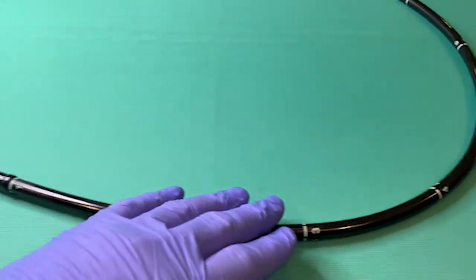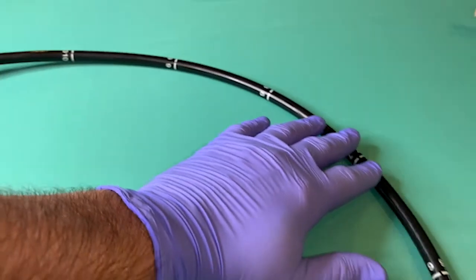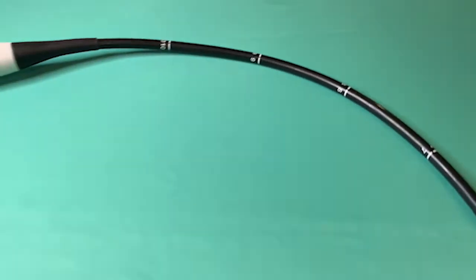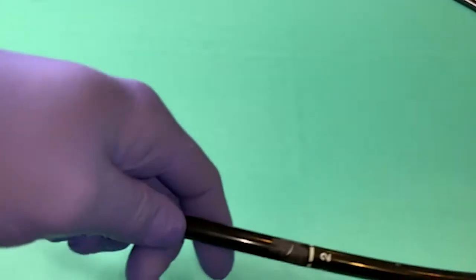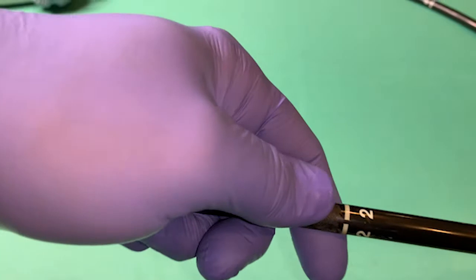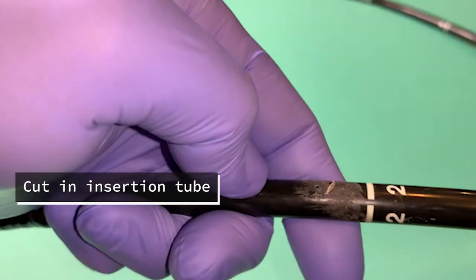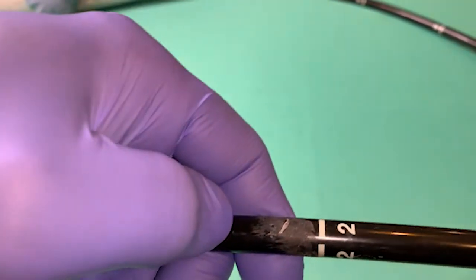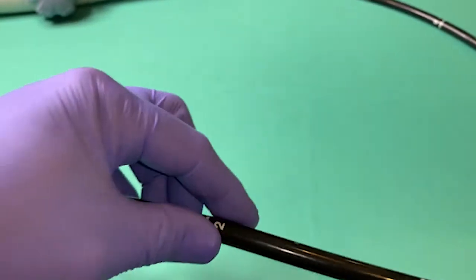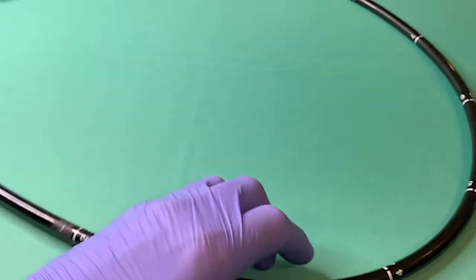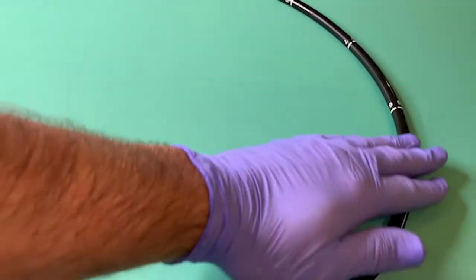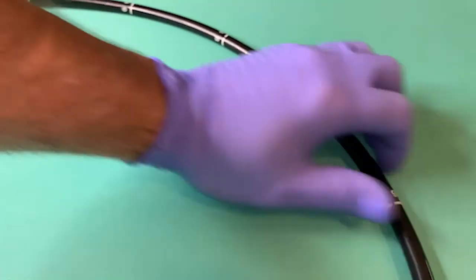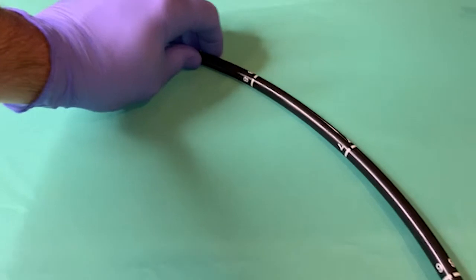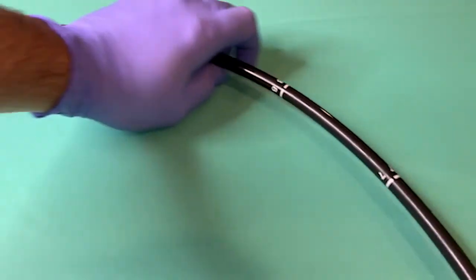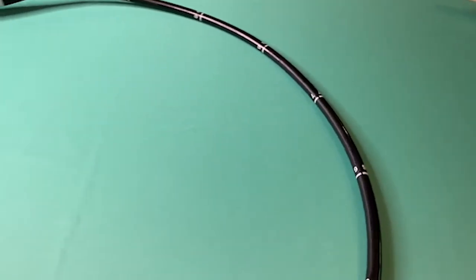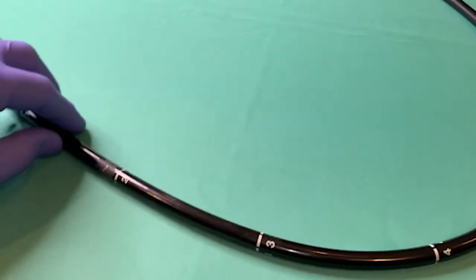Visually inspect the insertion tube for defects such as cuts, crushes, dents, and deep gouges. Run your hand along the entire length of the tube, feeling for abnormalities. Any area that is believed would allow fluid entry should be addressed with a high priority. Physical damage to the tube may affect internal systems including angulation mechanics and electrical wiring. Flex the insertion tube at multiple locations, inspecting for buckling. Buckles may be large and obvious, or may appear as small wrinkles.